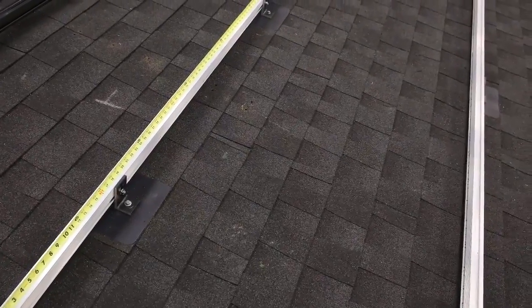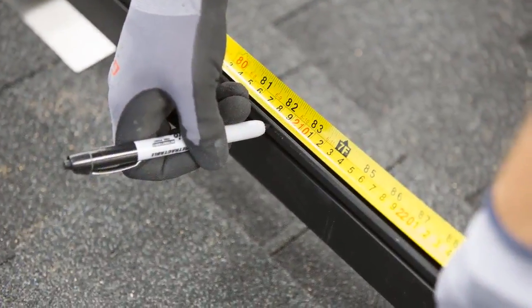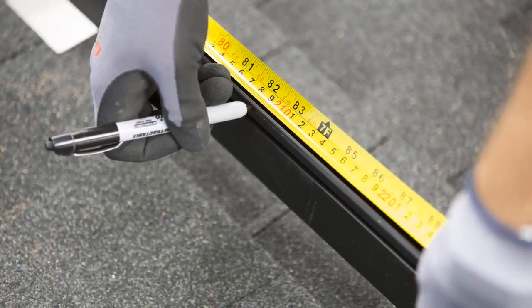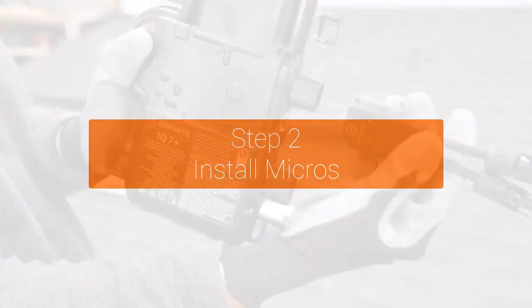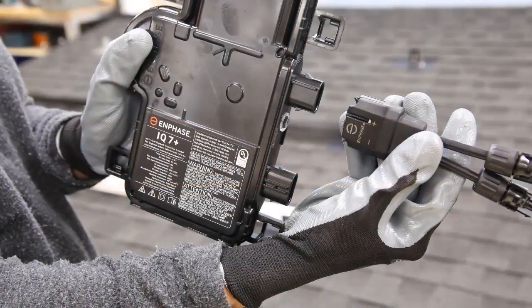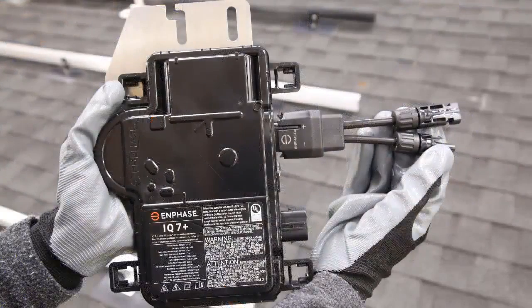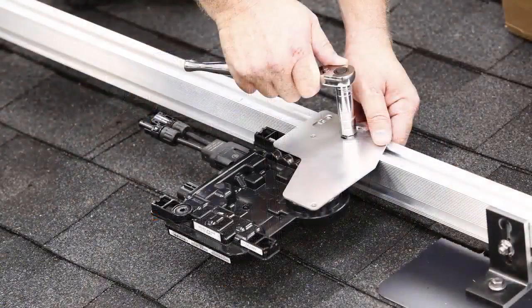Measure the modules and mark the approximate centers of each PV module on the PV racking to prepare for microinverter installation. If the Enphase DC adapter cables are not already attached, attach them to the DC input port of the microinverters now. Verify that the DC adapter cables are fully seated and locked. Listen for the click to verify. Mount the microinverters where you marked the rails, with the bracket side facing the sky.